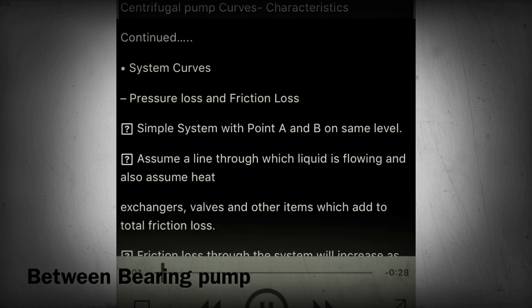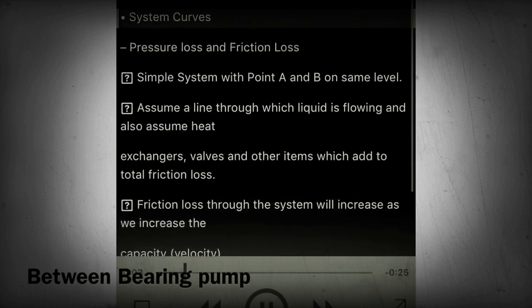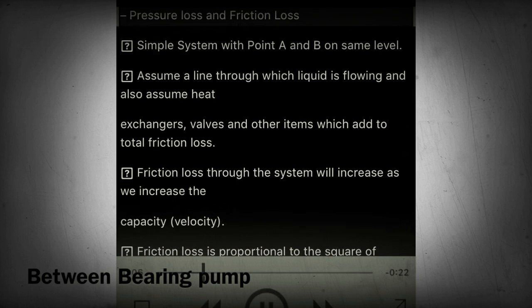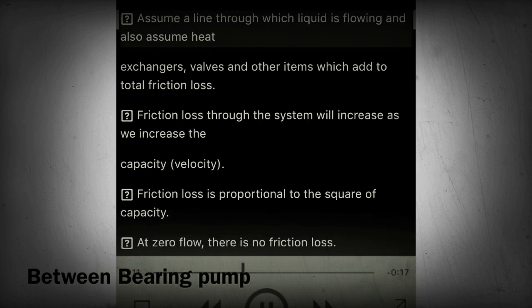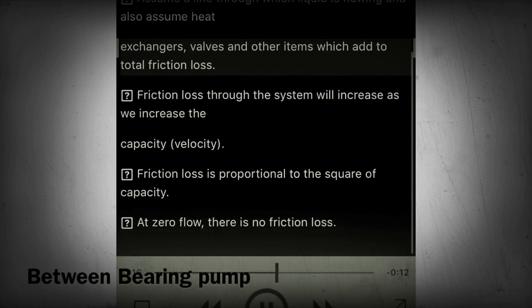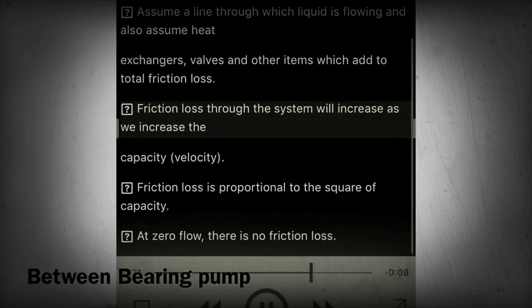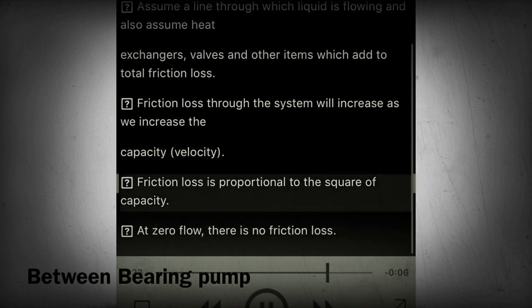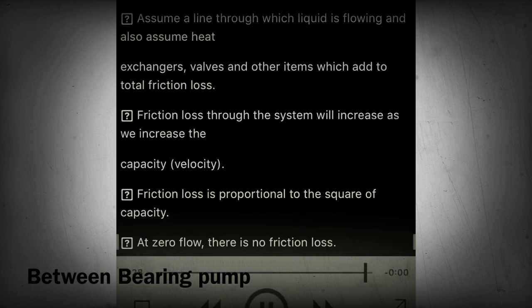Sections 29-30 - System curves: pressure loss and friction loss. For a simple system with points A and B at the same level, assume a line through which liquid is flowing with heat exchangers, valves, and other items that add to total friction loss. Friction loss through the system will increase as we increase the capacity. Velocity friction loss is proportional to the square of capacity; at zero flow there is no friction loss.